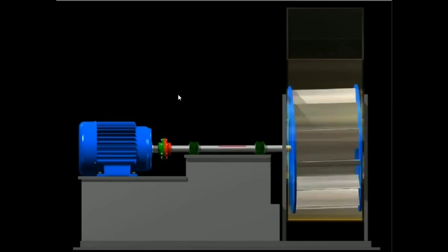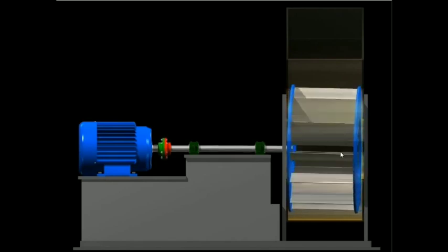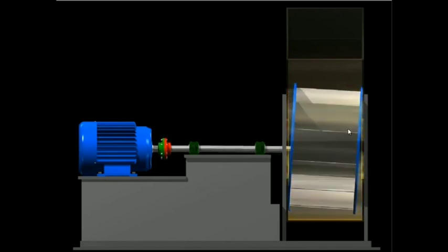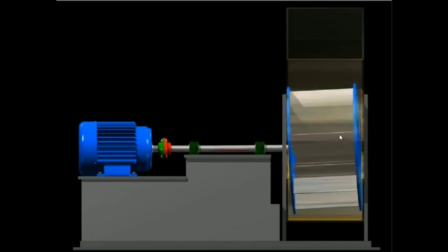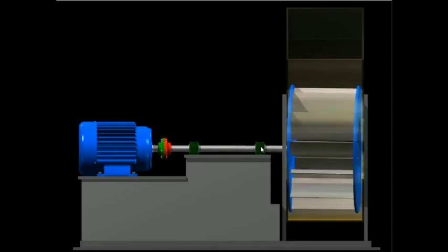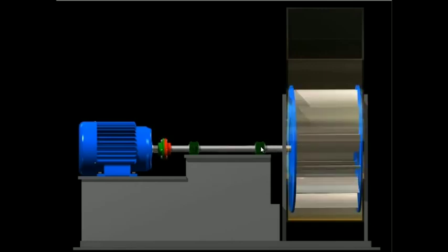In the case of overhung unbalance, we still get the radial motion. We still get that circular motion. What I'm highlighting here is that we also get a rocking motion, and that causes axial vibration. So the difference is we expect to see high vertical and horizontal vibration and high axial.